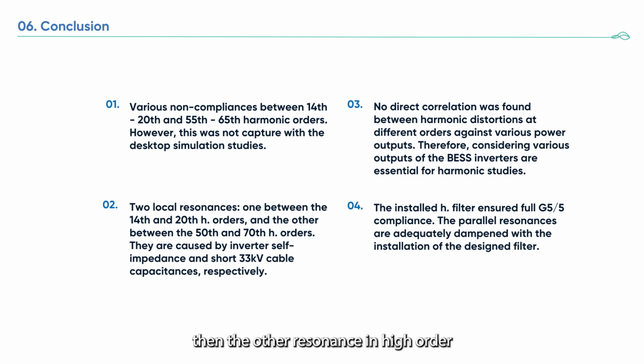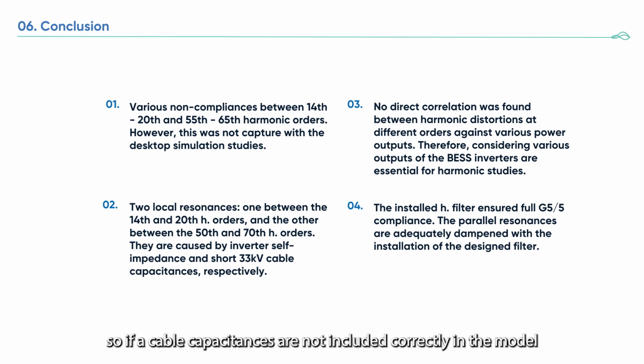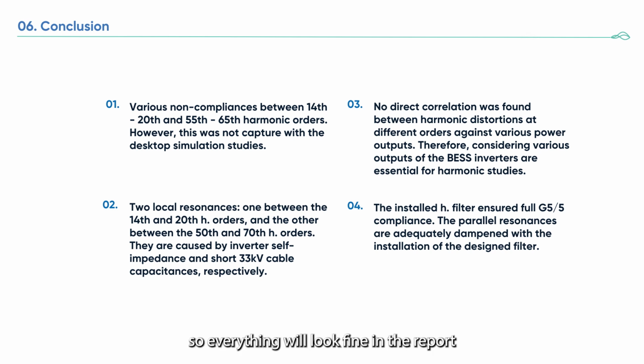Then the other resonance at high order. As I mentioned earlier, this system was dominantly inductive. So reactive part of the system was quite high. And at 33 kV network, our 33 kV cables were quite short. Total length was less than 1 kilometer. And this high frequency resonance was caused by an interaction between cable capacitance and network reactance. So if cable capacitances are not included correctly in the model, there is no way to detect that resonance. So everything will look fine in the report.